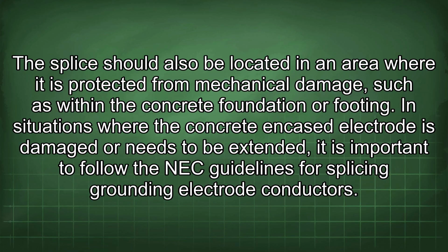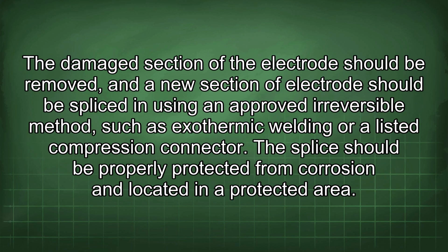In situations where the concrete encased electrode is damaged or needs to be extended, it is important to follow the NEC guidelines for splicing grounding electrode conductors. The damaged section of the electrode should be removed, and a new section of electrode should be spliced in using an approved irreversible method, such as exothermic welding or a listed compression connector. The splice should be properly protected from corrosion and located in a protected area.